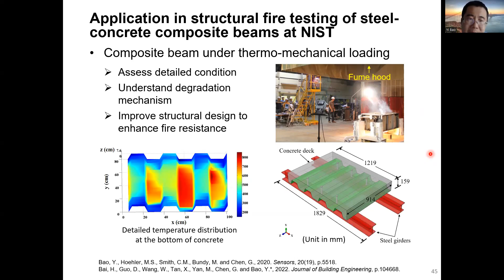As you can see, the temperature field within the material is actually pretty complicated. It's not uniform, it's not symmetrical. This method can greatly improve the thermomechanical analysis accuracy and efficiency. And based on the research for small-scale composite structures, we have applied the technology to some full-scale specimens for the floor beam project. In this project, we installed the fiber optic sensors inside the concrete slab and also attached to the surface of steel beam. But the steel beam was covered using some sort of materials for fire protection for the steel. So the fiber optic sensor was actually in direct contact to the steel, but covered by the fireproofing composite.